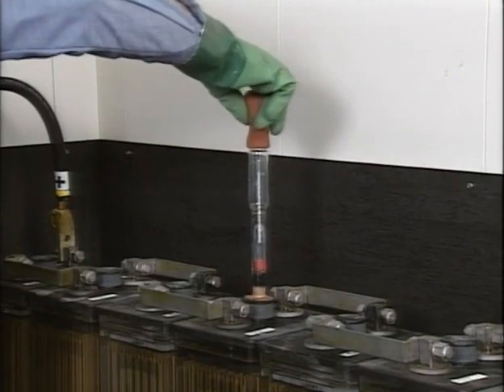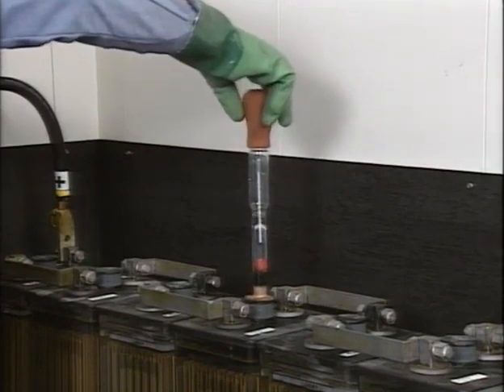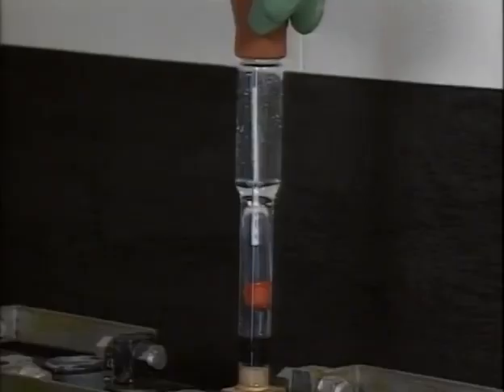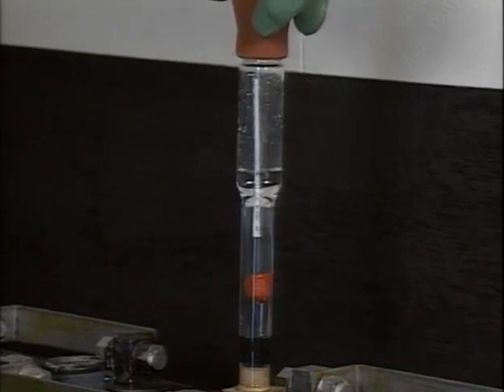While a sample is being drawn, the syringe is held vertically so the float doesn't touch the sides of the barrel. Enough electrolyte is drawn to lift the float off the bottom of the barrel, but not so much that the float hits the top of the barrel.